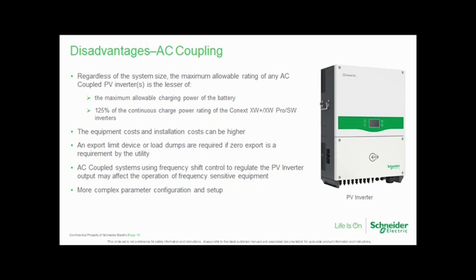There's also going to be higher equipment costs and installation costs due to the additional programming for both the XW Plus as well as the PV inverter. Because you can't stop exporting when you're AC coupling, you may have to put in an export limit device or load dumps if you require a zero export solution by the utility.